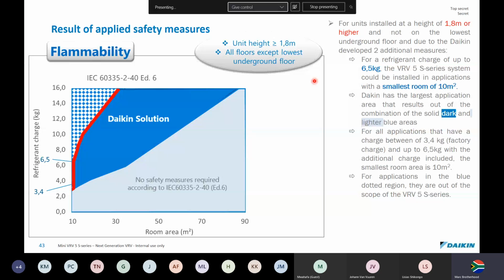Excuse me. So what they've said is that for a refrigerant charge of up to 6.5 kilograms, if you've got 90 to 110 meter pipe runs, the VRV5S system can be installed in applications with a room as small as 10 square meters. Okay, I know this seems a bit complicated. It's the first time you're seeing these graphs, but if you read through it and go a bit slowly, you should understand it.